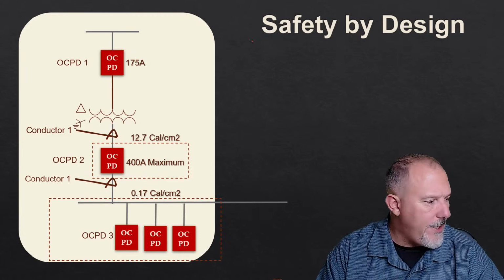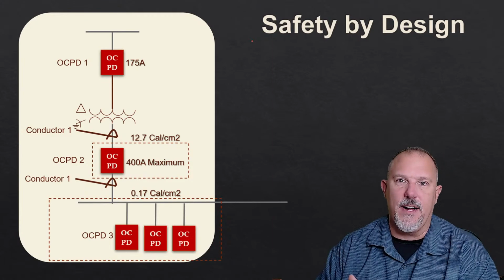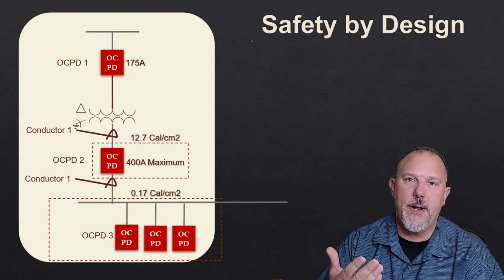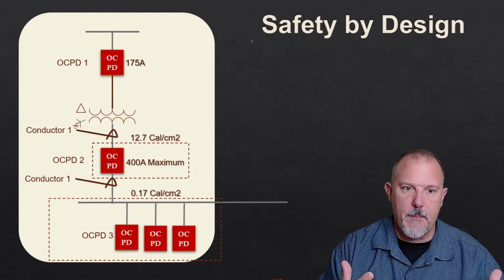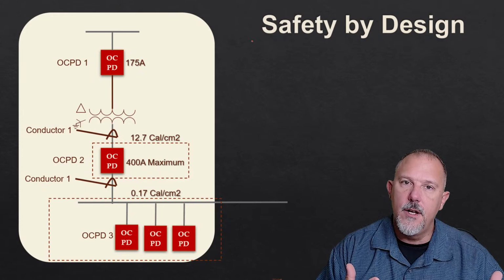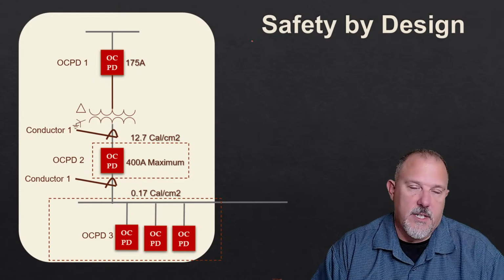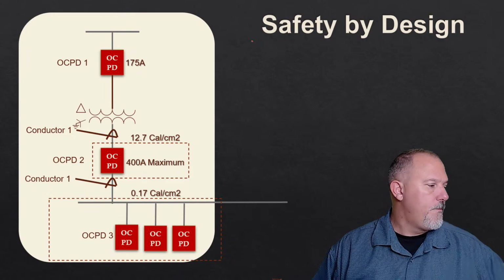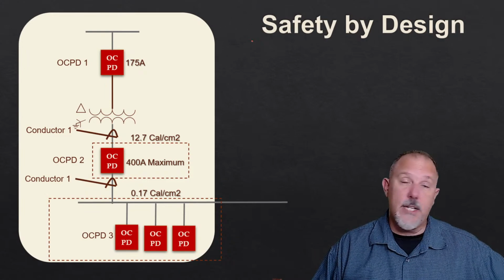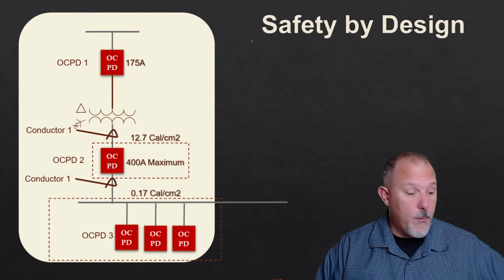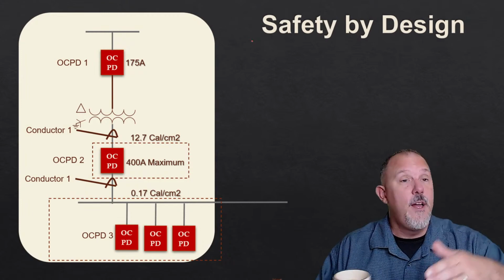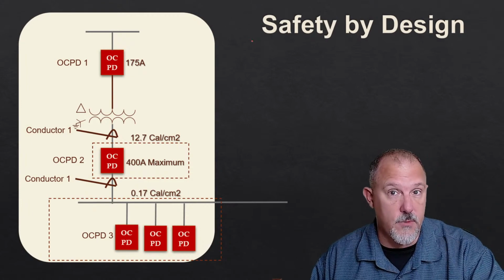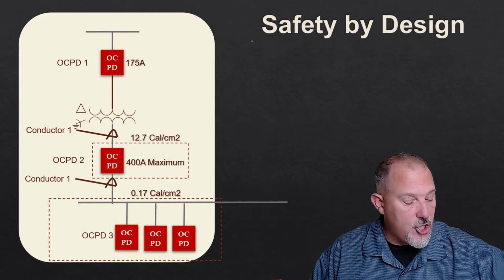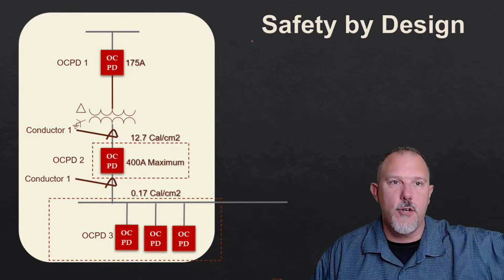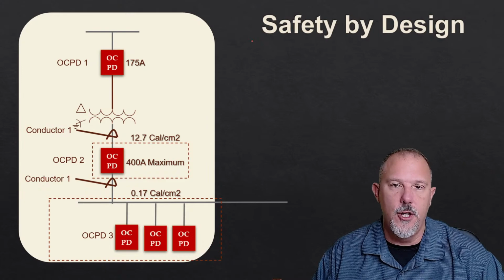So you scratch your head and say, how can I justify, if I have a main, I've got to put a barrier, but I have 6 disconnects and I'm staring at bare copper conductors, bus, and there's no protection. Why? Because I physically can't cover it. So they basically said, look, we need to go into 230 and put some requirements for the 6 disconnect rule. They didn't want to remove the 6 disconnect rule. They just wanted to make sure that you had a main overcurrent device in each of those enclosures.